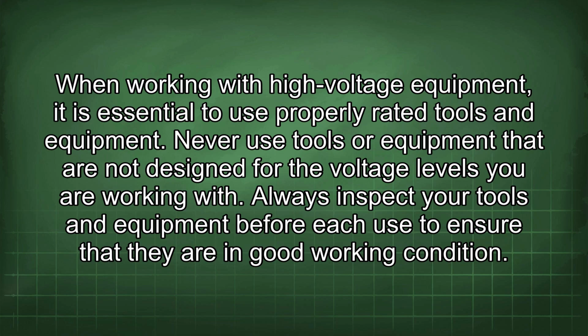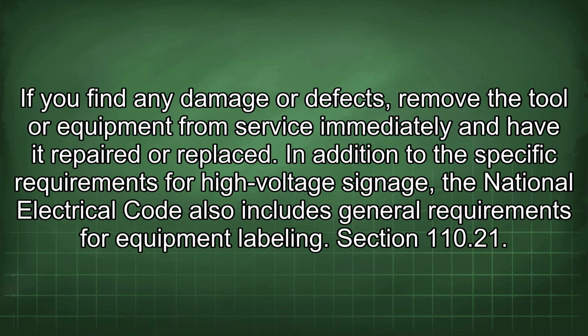When working with high voltage equipment, it is essential to use properly rated tools and equipment. Never use tools or equipment that are not designed for the voltage levels you are working with. Always inspect your tools and equipment before each use to ensure that they are in good working condition. If you find any damage or defects, remove the tool or equipment from service immediately and have it repaired or replaced.